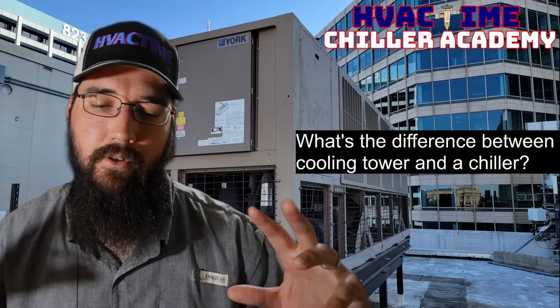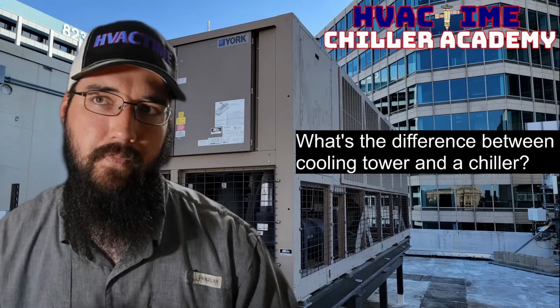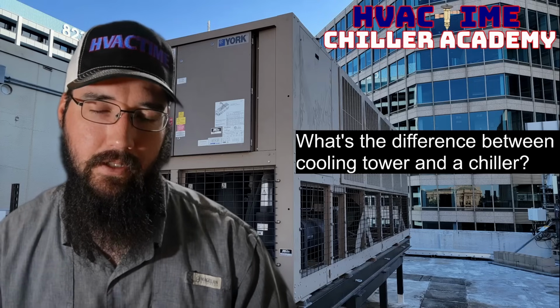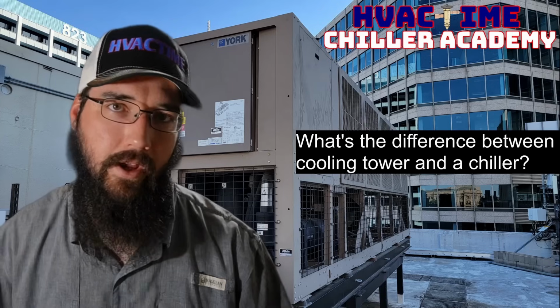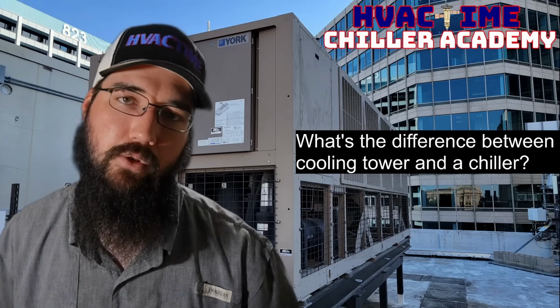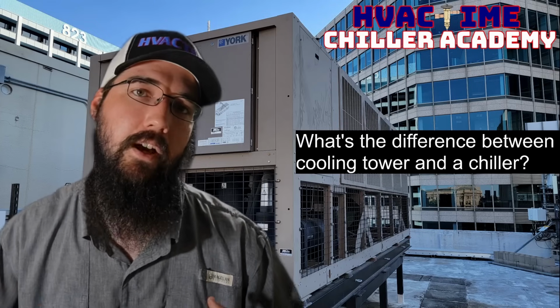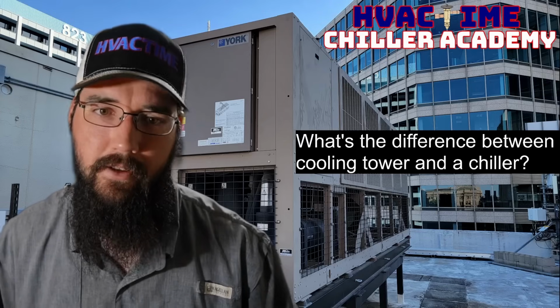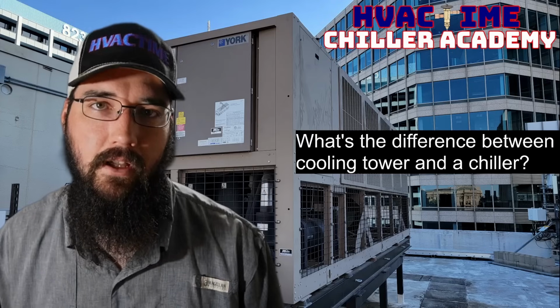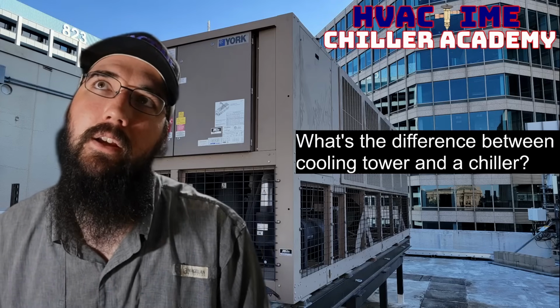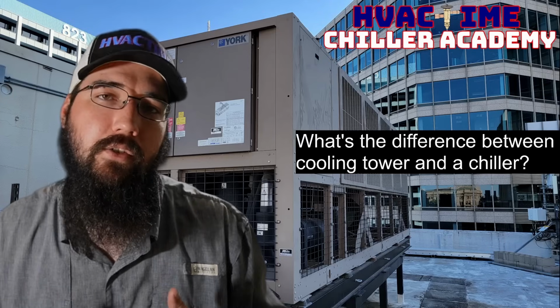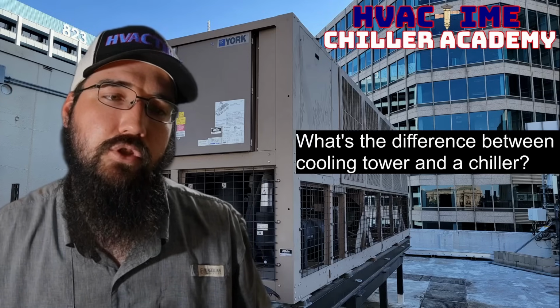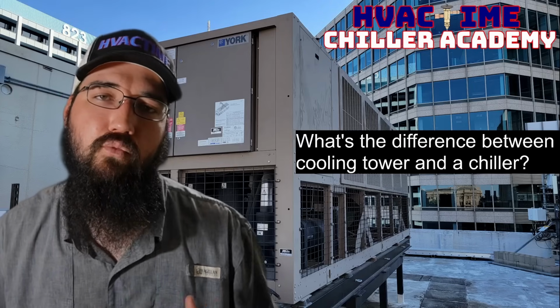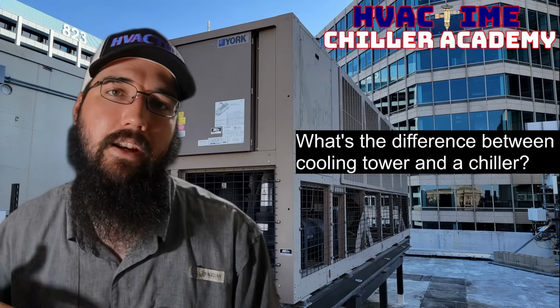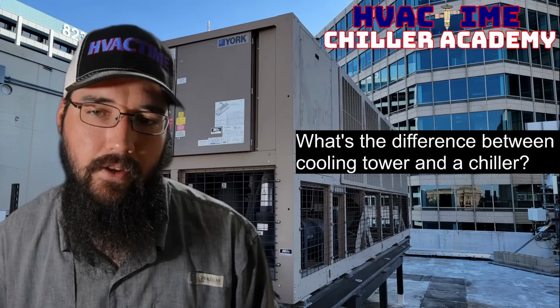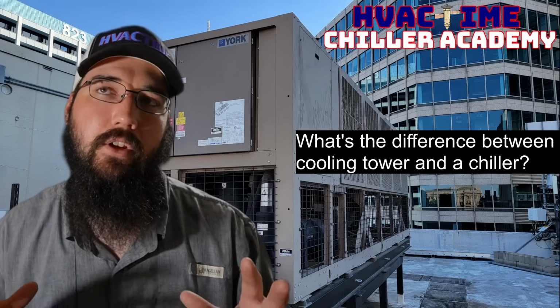But essentially a cooling tower is just cooling water, usually condenser water specifically, or water that we're using to cool a condenser. Now we could get way off into the weeds on specialty applications and how they can be used as an economizer function. Then we start talking open loop and closed loop towers. And we could get way off into the weeds here. Sorry about the mic there. But on a basic level, that's what it's doing. This cooling tower is serving the chiller or internal cooling equipment by rejecting its condenser heat instead of having an air over condenser coil or something to that effect. That is what our tower is doing. That is where they're separate.